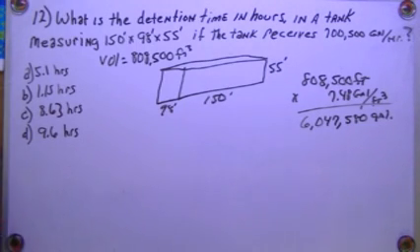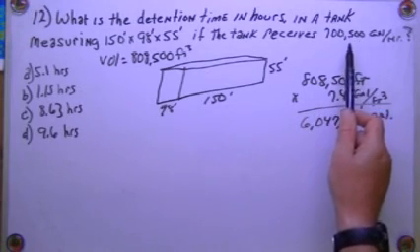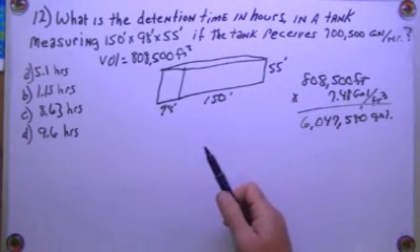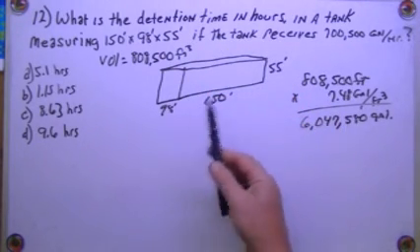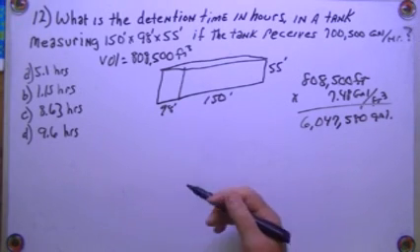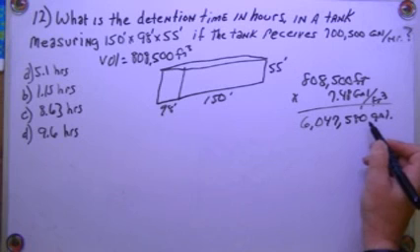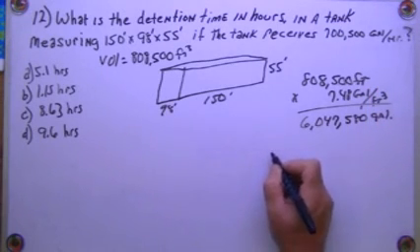That's a 6,000,000 gallon tank, and if I'm going to get 700,000 gallons per hour, the detention time is, the detention and retention time, it's the time it takes to fill or empty a tank, it doesn't really matter. So I'm going to take this 6,000,000 gallons and divide it by 700,500 gallons per hour.